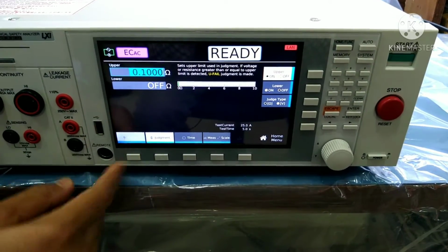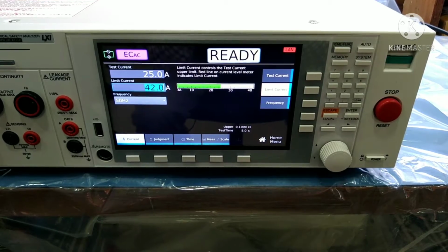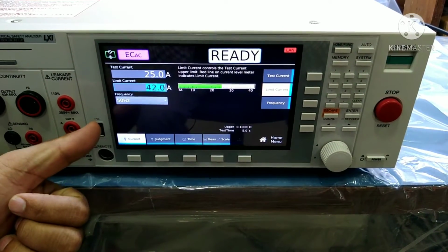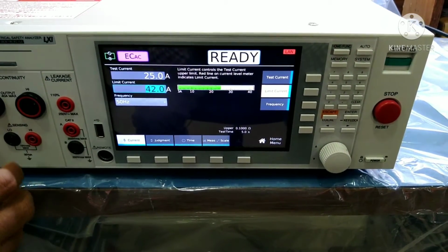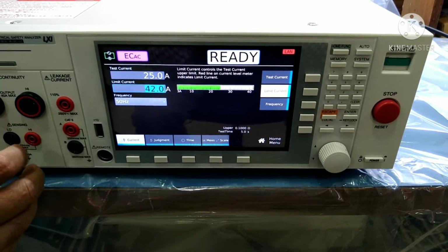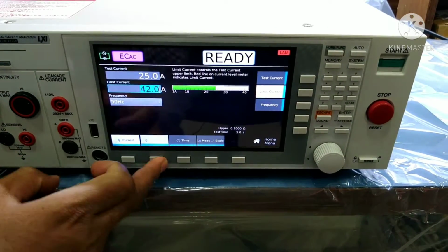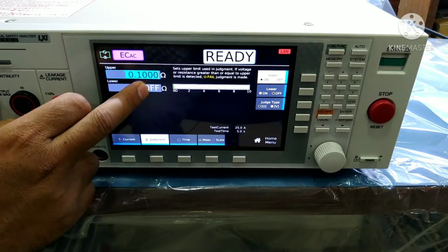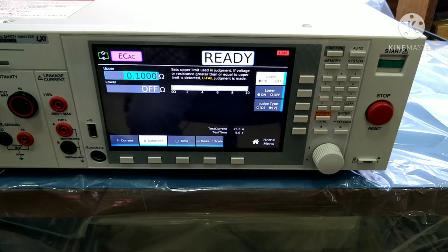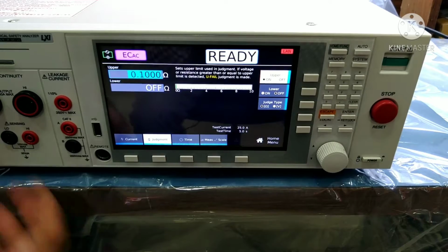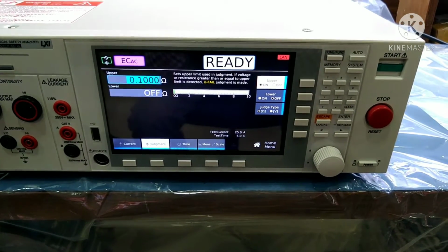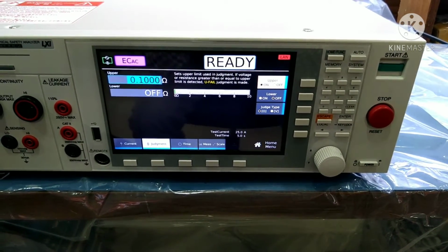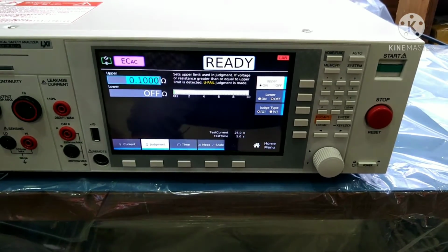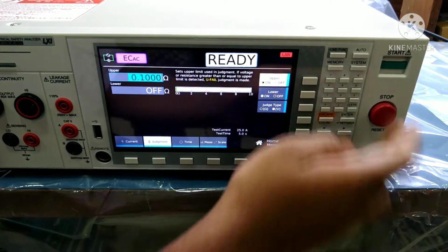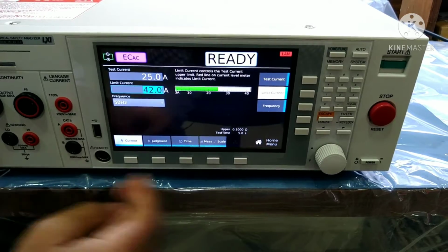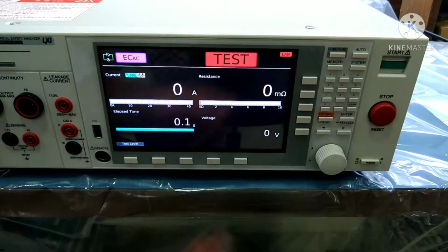This setting is very important. For the earth continuity testers, the circuit is open. Open means the resistance will be infinite, but we have set 0.1, which is a very low resistance value. That means it will show fail. If you connect something like a probe or DUT, according to the test it will show pass. So now I'm starting the test, it will show fail.